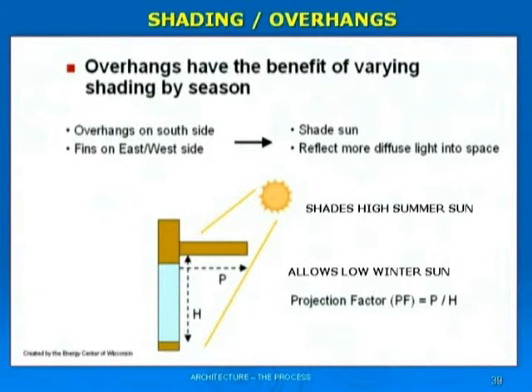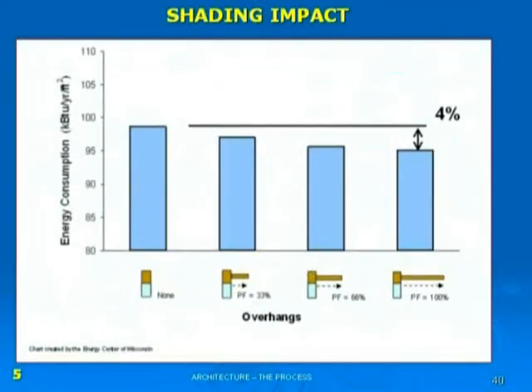The shade produced by the overhang keeps the summer sun out. If you have the relationship of the projection P and the height of the window H equal to 100%, you can save 4% at minimum off your air conditioning load. So just by merely adding a projection, you're saving 4% every single summer season. What does it cost to put the projection on? It's going to cost you something. But if you look at it in the total analysis — if you're going to stay in that building 10 years, 20 years, or if it's a rental situation going on for 75 years — that projection is making money for you.